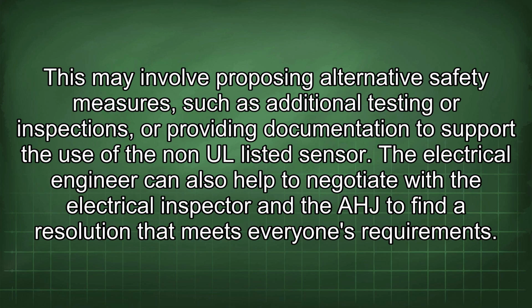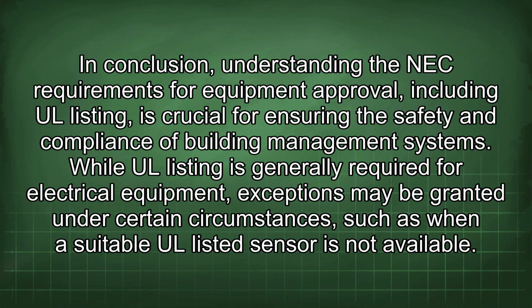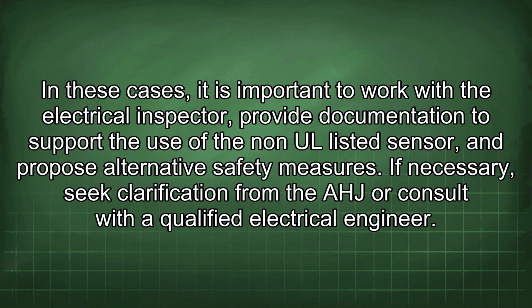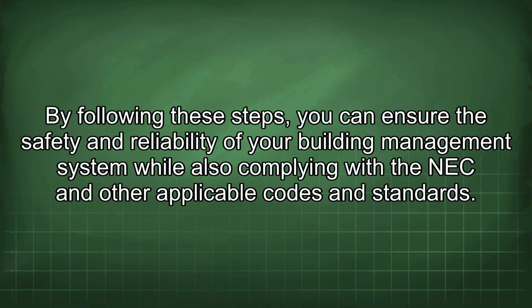meets everyone's requirements. In conclusion, understanding the NEC requirements for equipment approval, including UL listing, is crucial for ensuring the safety and compliance of building management systems. While UL listing is generally required for electrical equipment, exceptions may be granted under certain circumstances, such as when a suitable UL listed sensor is not available. In these cases, it is important to work with the electrical inspector, provide documentation to support the use of the non-UL listed sensor, and propose alternative safety measures. If necessary, seek clarification from the AHJ or consult with a qualified electrical engineer. By following these steps, you can ensure the safety and reliability of your building management system while also complying with the NEC and other applicable codes and standards.